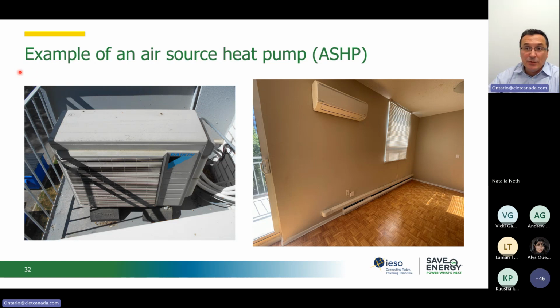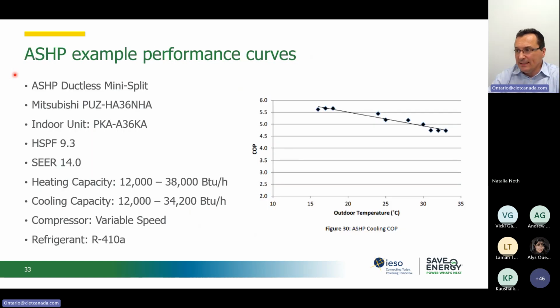Now, I mentioned that temperature is very important for this, because the set points for spaces are usually within a certain small margin, but outdoor temperature changes tremendously in our climate. We go from -16, as we've seen yesterday, even lower than that, and we go all the way up to +35. So we have a large range of temperatures, and therefore we see the efficiency of the heat pump impacted by that temperature. So for that reason, there were studies done to see what exactly it means for efficiency. And as you see here, an example for a unit that was part of one of these studies.